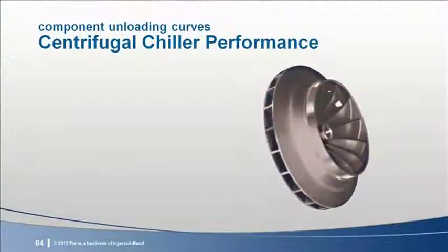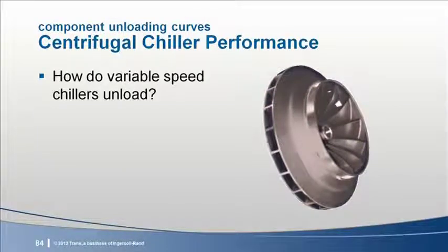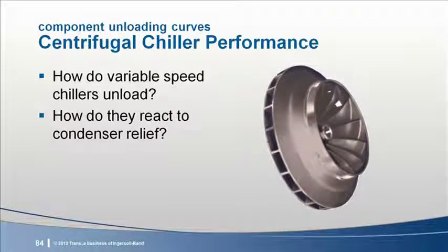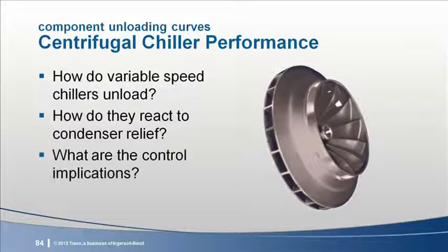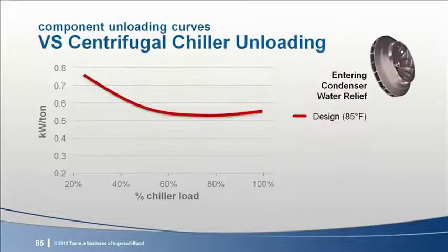Let's look at variable speed drive centrifugal performance from 3 perspectives: how they unload with constant lift, how they react to reduced lift, and then what are the control implications. Here is the unloading line of a variable speed chiller selected and being controlled to a constant 85-degree entering condenser water. What is interesting about this line is that if you compare it to the unloading line of a constant speed chiller, it would be very similar.